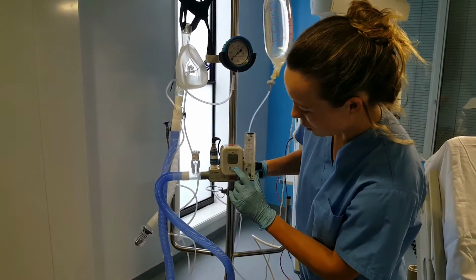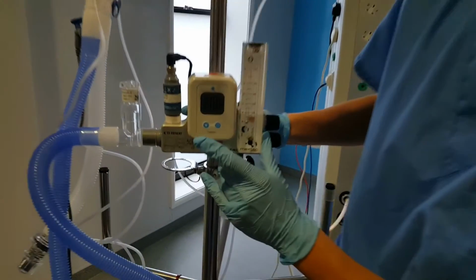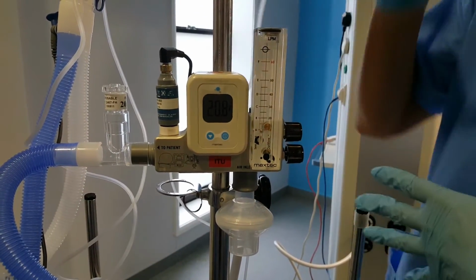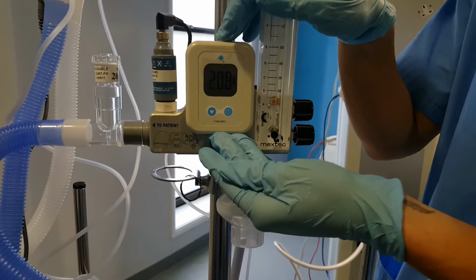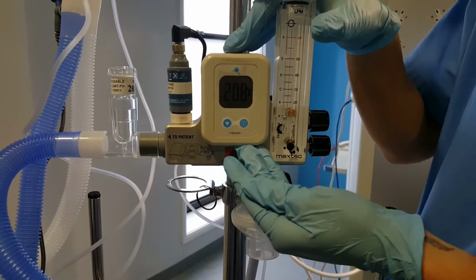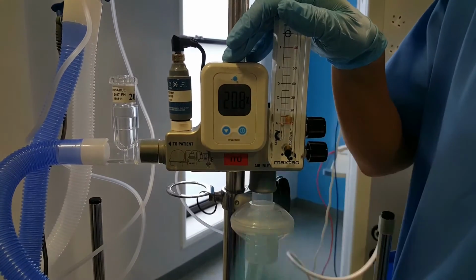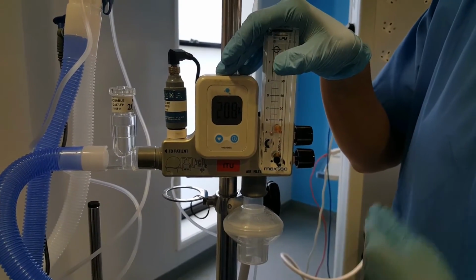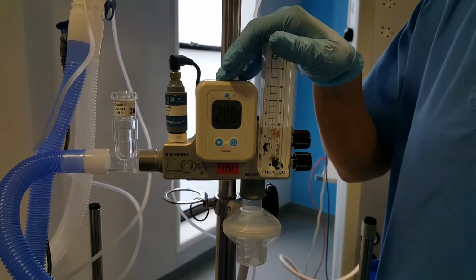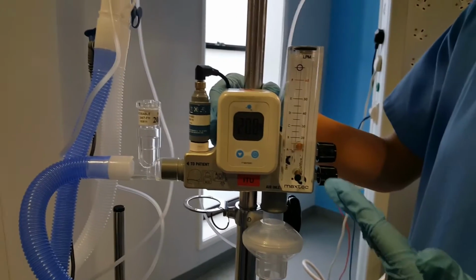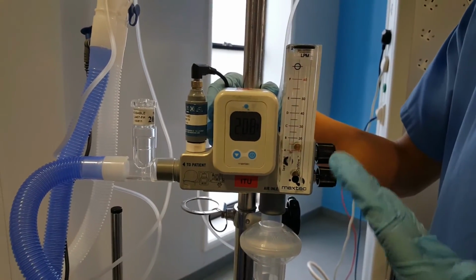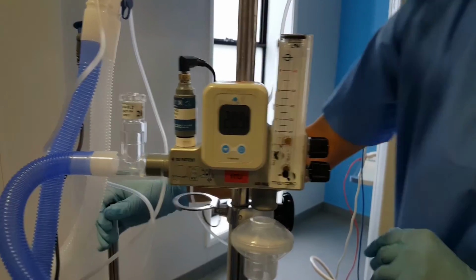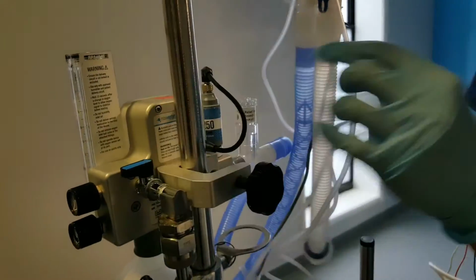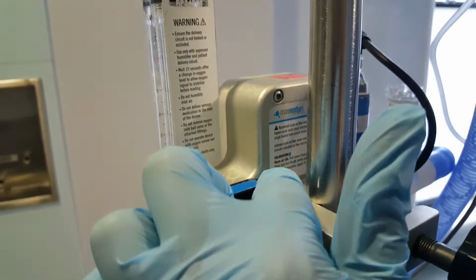We will turn this on, so you hit the on button, and you'll need to calibrate it. This is on battery, it's not mains power, so if it does not work, it may mean that the battery is gone and you'll need to return it to the intensive care unit. Otherwise you won't know how much oxygen flow you're giving to your patient. So you need to calibrate this first to make sure you're giving accurate oxygen, and it has to be calibrated every time you switch it on and off. There are very small instructions at the very back if you do forget how to calibrate it, which you can read. It can be quite difficult to see, it's just here.